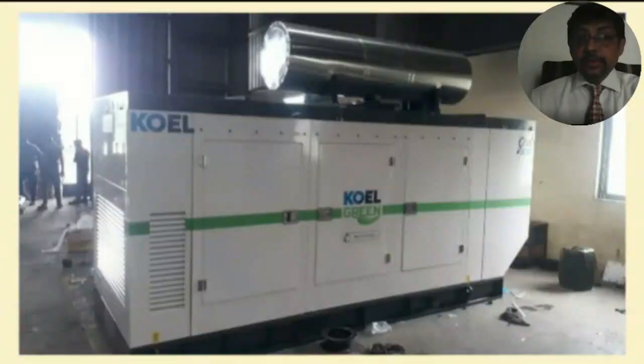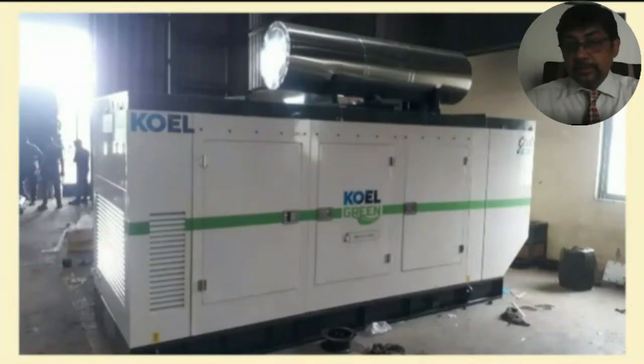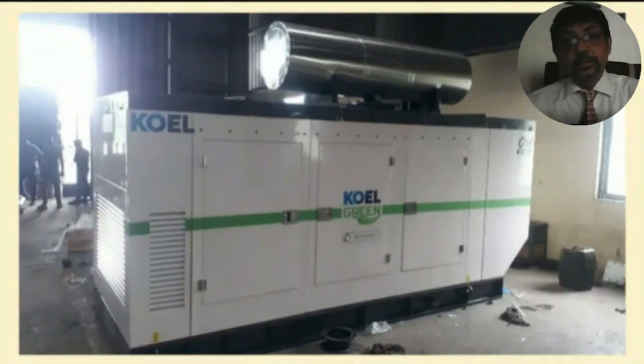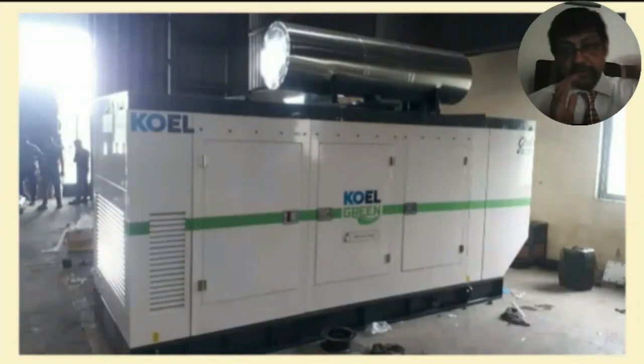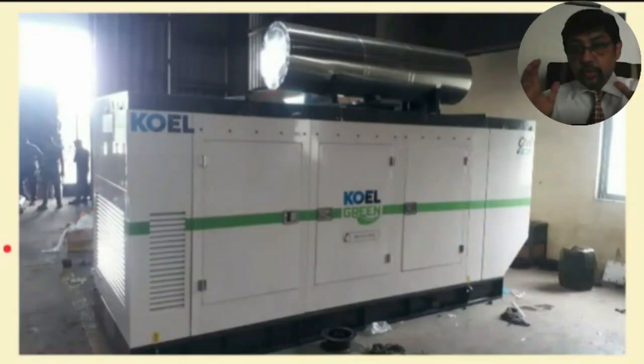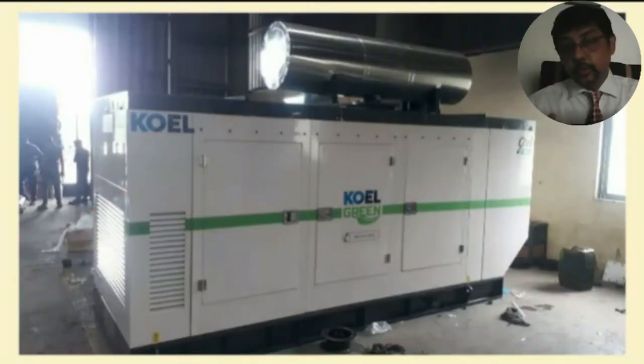Yeah, next. Here we can see a very clear silencer mounted on the generator and the base frame, then the acoustic enclosure and the silencer. The silencer has aluminium cladding. This aluminium cladding is given so that heat dissipation is taken care of, along with the glass wool or asbestos filled inside the cladding, so that no more heat is dissipated in the room, and the generator efficiency is good.